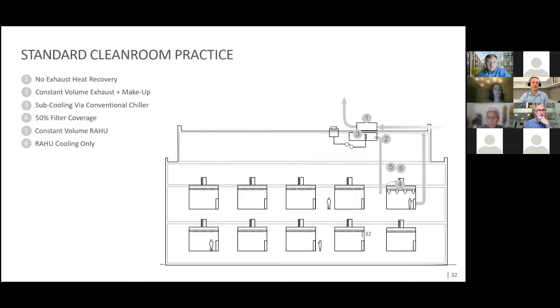That's just one example on this list: they didn't have heat recovery because there were extremely corrosive materials in the exhaust, they didn't have variable volume airflow, and they had huge pressure drops pushing that tremendous amount of air through just a certain percent of the ceiling being covered with filters in the clean room. So there are all these missed opportunities in the business-as-usual practice for clean rooms.